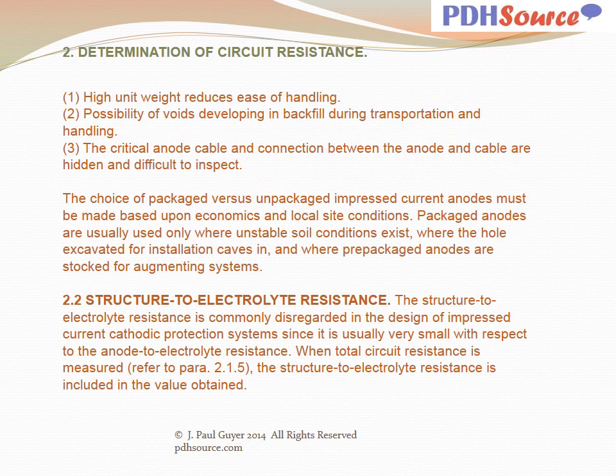First, high unit weight reduces ease of handling. Second, possibility of voids developing in backfill during transportation and handling. And third, the critical anode cable and connection between the anode and cable are hidden and difficult to inspect.